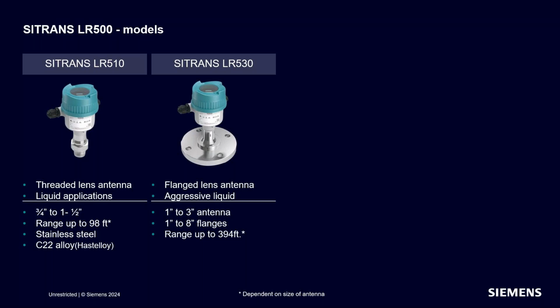Then there's the 530. The 530 is our flanged antenna version. This would be the equivalent to what had been the LR250 series. It's designed for liquid chemical applications. The antenna lens and seals are PTFE. The maximum range for this model is 394 feet, depending upon which size flange and antenna we choose.